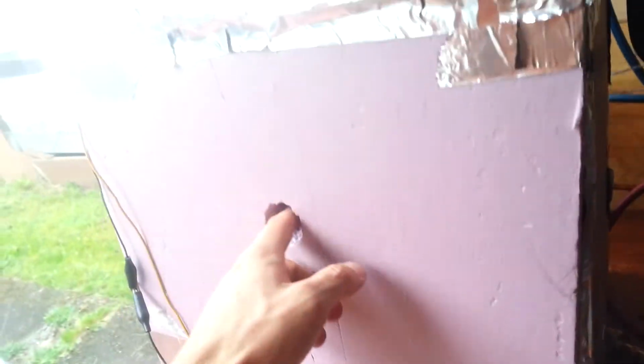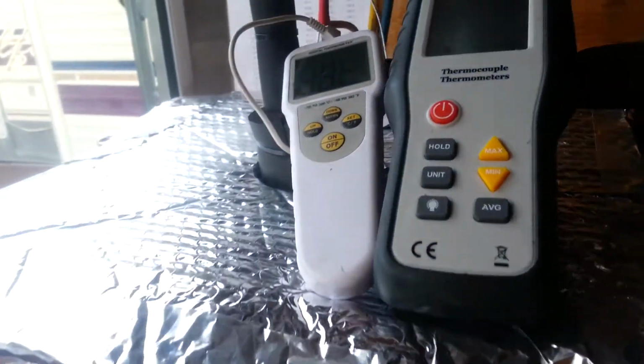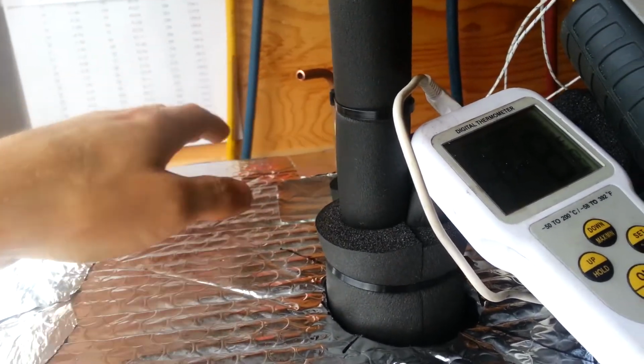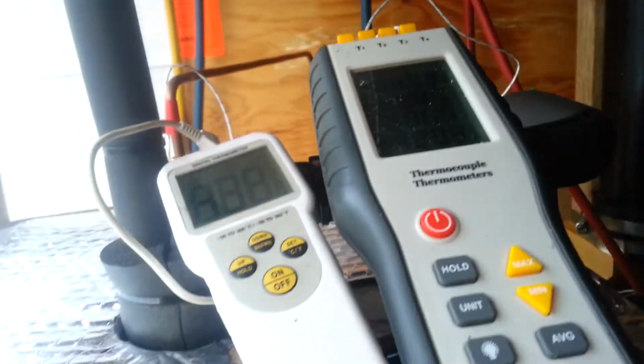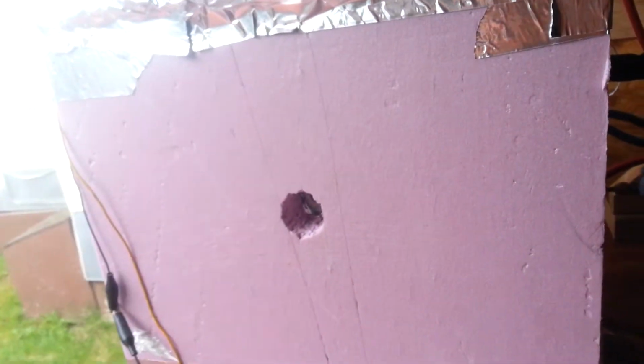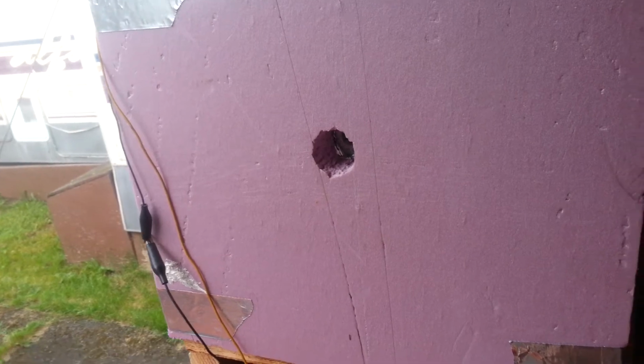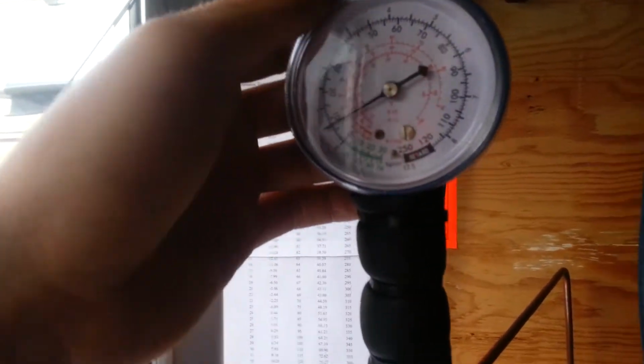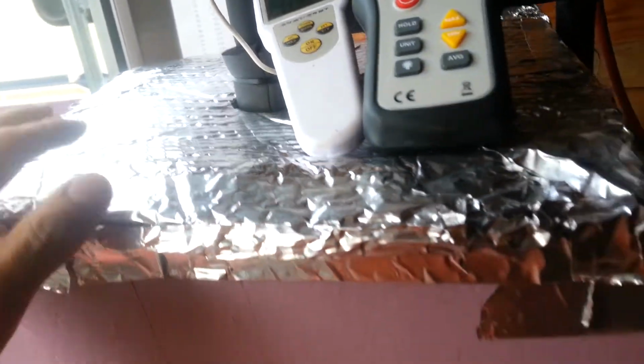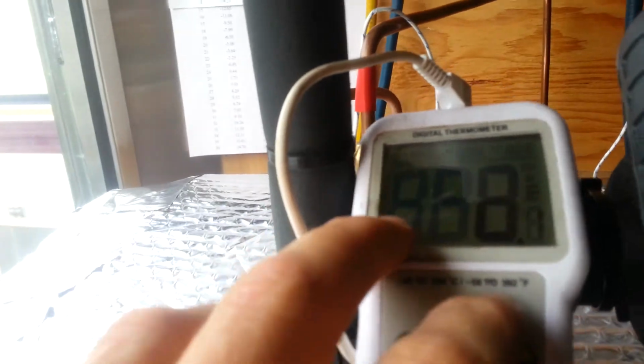And at these really low pressures, I actually start to see if I can actually see it. I can't even make it out. No, I don't really see anything in there other than a little bit of turbulent vapor. So it is in a little bit of a dry condition. Now, ideally, I can run this thing in such a condition that I open the throttle up a little bit, allowing the pressure to rise quite a bit, and it'll actually get to the point where I can maintain that liquid level in there and adjust the throttling valve every 10 minutes or so just to keep it there. But the suction temperature associated with the pressure will be maybe just a few degrees lower than the contents of the box. Right now, this temperature here is just the air temperature.